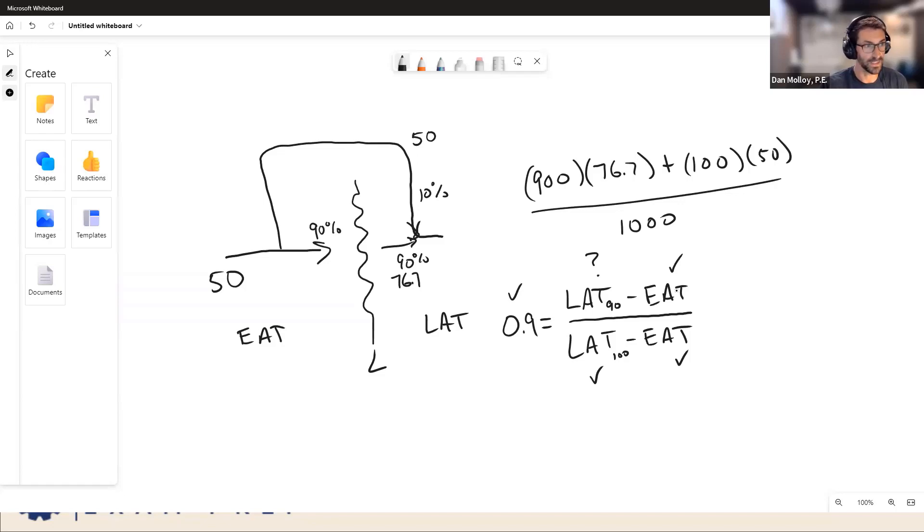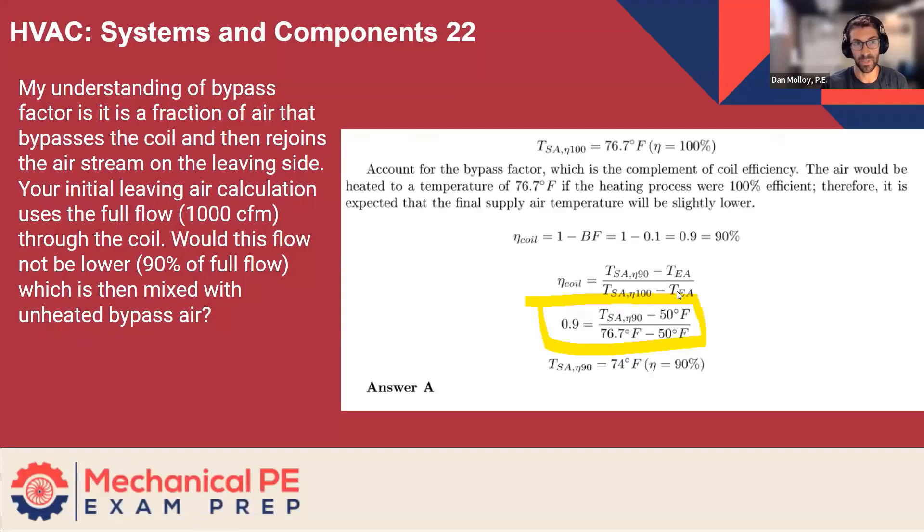And physically it's a lot more like what really happens because you can actually imagine that 10% of the volume of this air, the mass of this air, is getting past the coil without being impacted. So it's getting by and mixing. I shouldn't say it's like that. It is that, but from a calculation perspective, the concept of coil efficiency can be carried out in this manner. And that's perfectly acceptable to think.